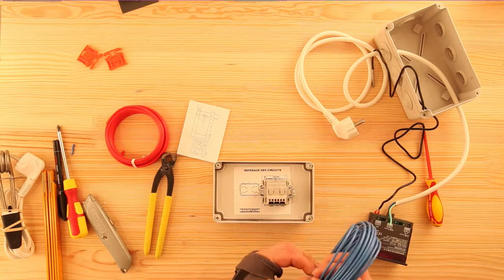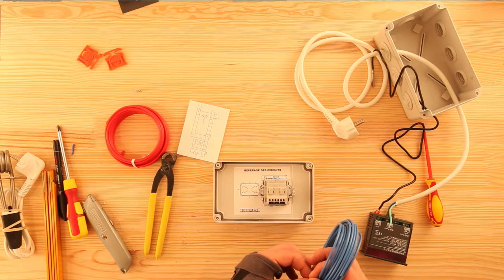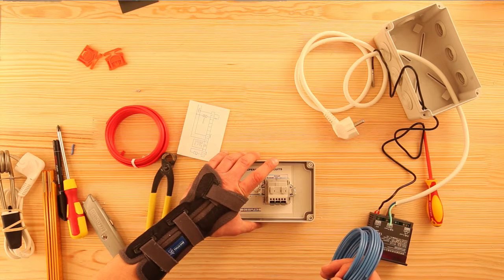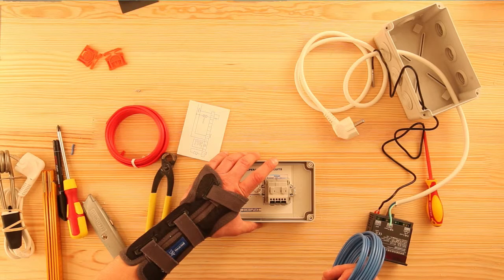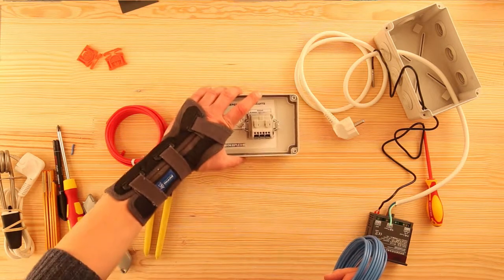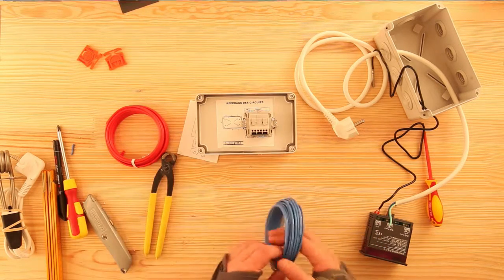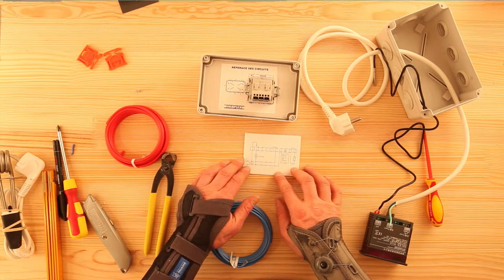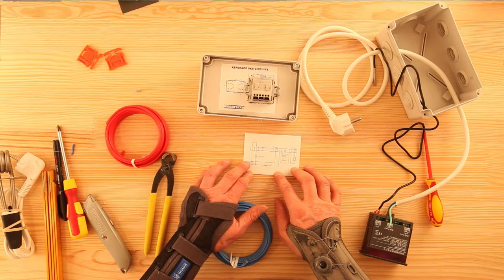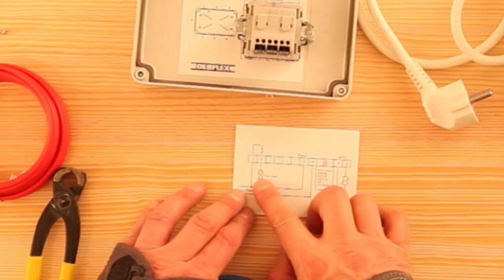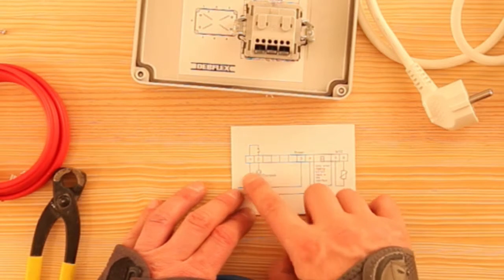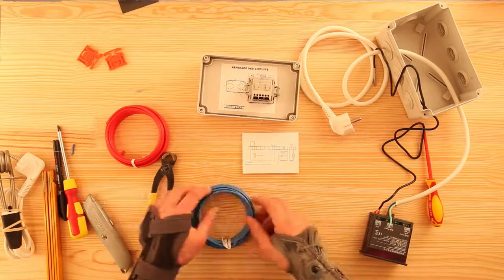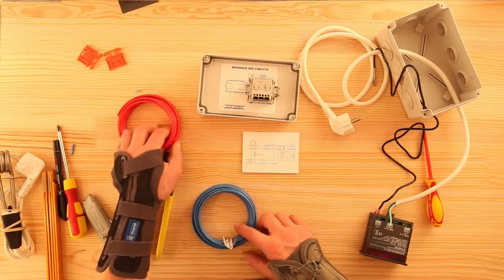With P the power, we have here 300 watts, so with a voltage of 220 volts, we have a bit more than 1 ampere. 1 ampere is quite a lot already, so I follow the rule of thumb which considers quite reasonable 1 ampere by square millimeter of copper cable cross-section. In order to keep some room for potential future use of heaters with a different load, I'm using 2.5 square millimeters cross-section cables. So these are fairly rigid cables. I use a blue cable for neutral and a brown or red cable for live or phase.